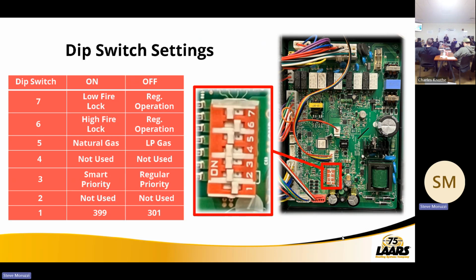Doesn't mean I can take a 301 and turn it into a 399, guys. Not happening. Heat exchanger is a little larger on the 399. There's some fan speeds that are different on the 301 versus 399. Dip switch 3, it's defaulted for smart priority. If you want to go back to traditional or regular priority, you may, okay?